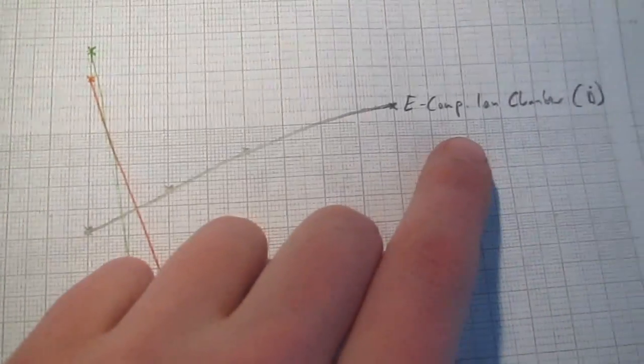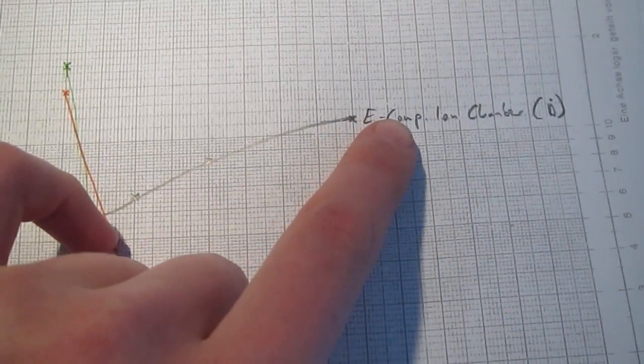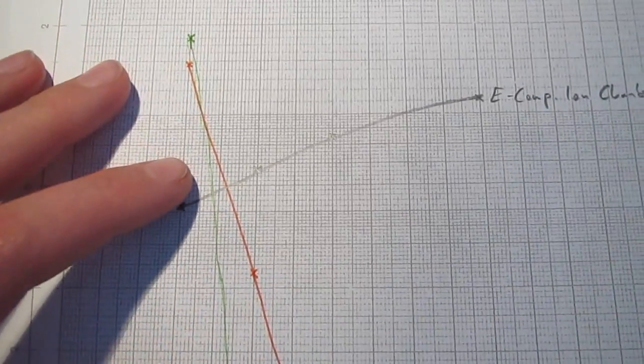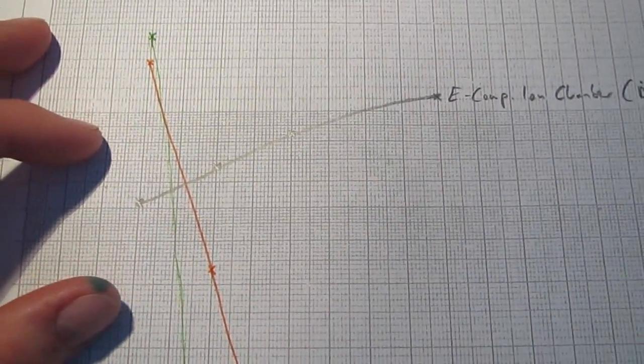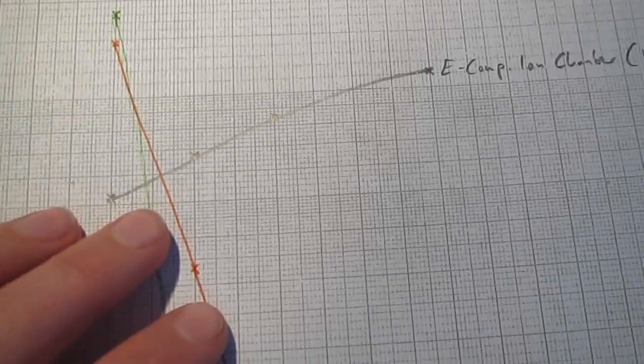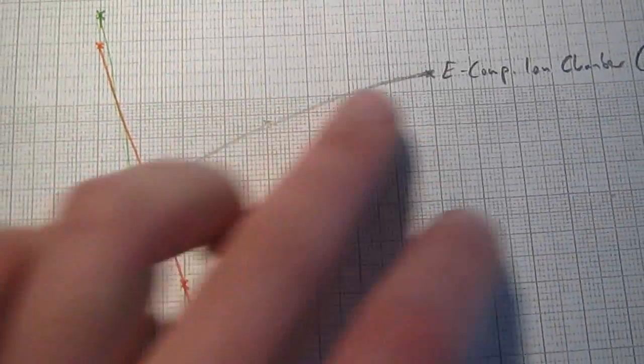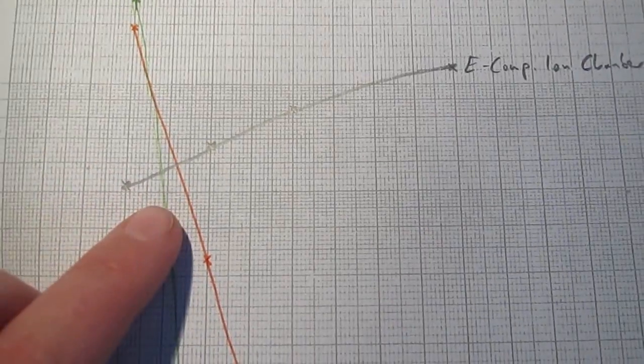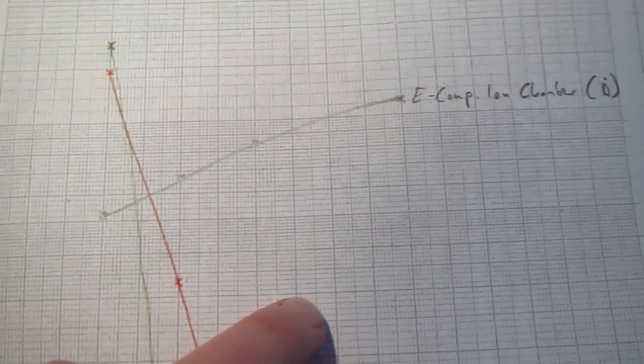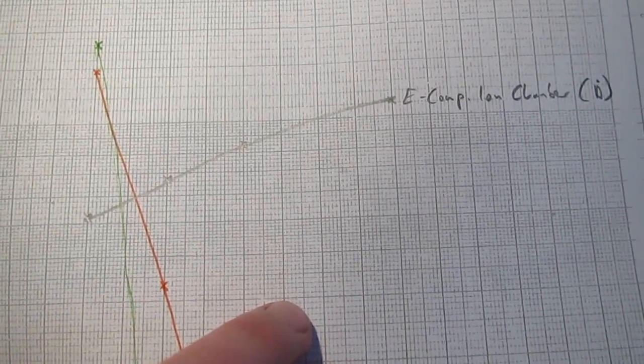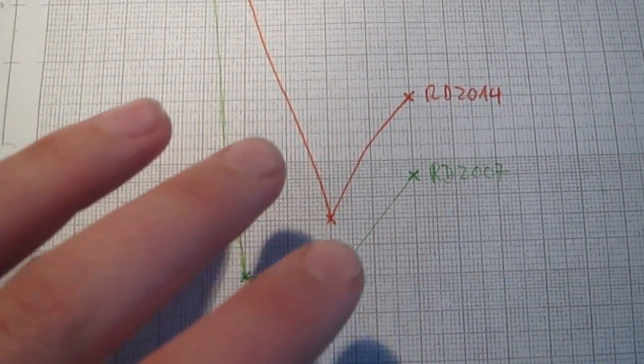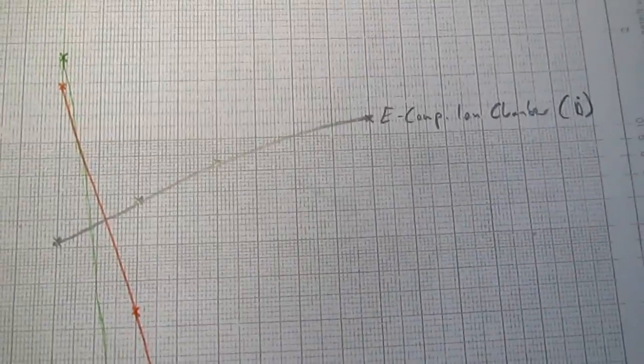So this would be the comparison reading with an energy compensated ion chamber. You actually expect pretty much an exponential function, not quite, but pretty much an exponential function, so on semi-log paper this would be almost linear. You can see an increase of the actual dose rate, as I said, in energy compensated ion chambers, so they have the same detection probability for higher energy photons as well as for lower energy photons. These detectors never claimed to have that, so it's just a rough comparison just so you get an idea of a different detector system.